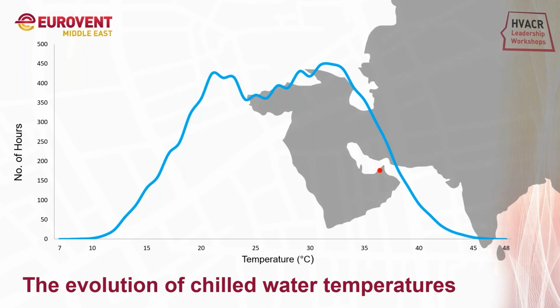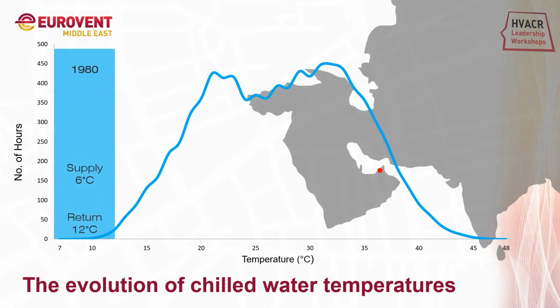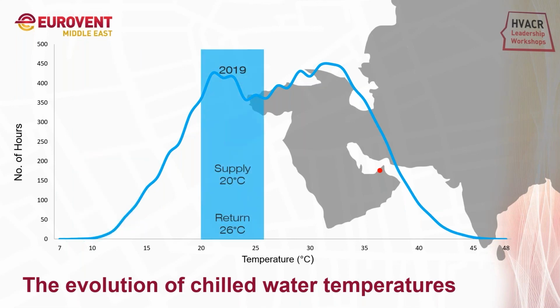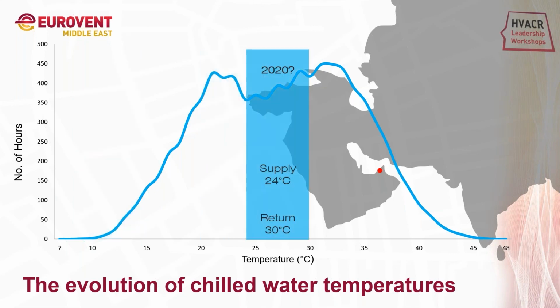Now let's see the evolution of the chilled water temperatures over the years. In the 1980s, we have seen a supply and return temperature of 6/12. From 1990 to 2000, we have seen the use of 7/12 degrees Celsius chilled water temperatures. In the year 2010, we have seen 8/14, then 20/26, and in 2020, it could be 24/30.